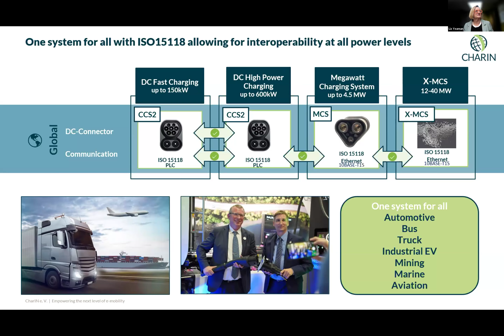There are actually three levels of MCS. What they're looking for the Auckland ferries is level 3 MCS, but level 1 is probably what we'll see on the first trucks that come with MCS to New Zealand. That can have an uncooled cable and uncooled inlet, as the maximum current is 350 amps. Level 2 goes up to 1,000 amps, requiring a cooled cable but still an uncooled inlet. Level 3 needs both a cooled cable and a cooled inlet to allow current to flow at up to 3,000 amps.